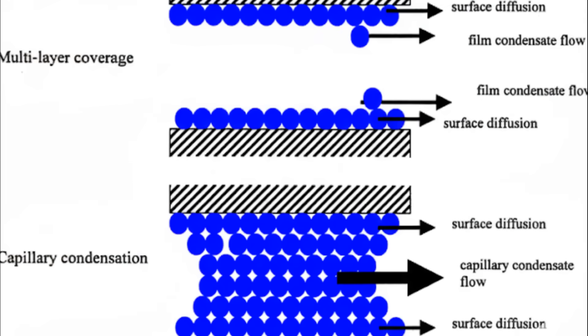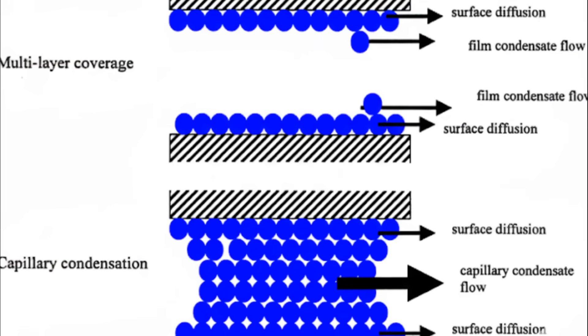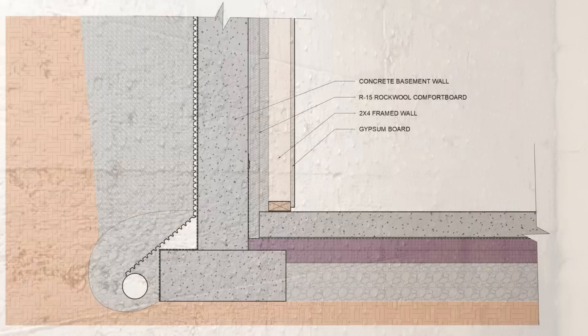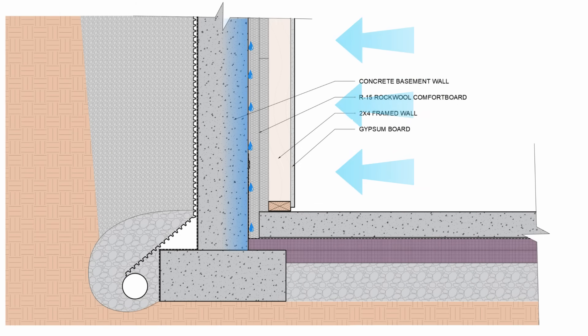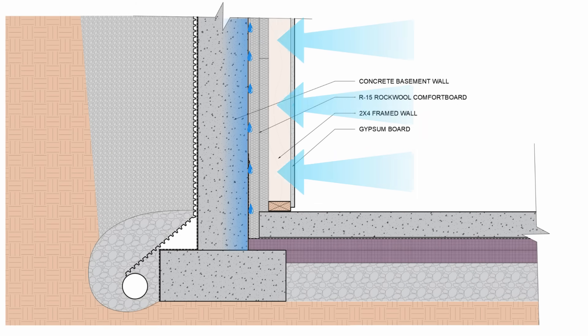Again, this is first going to appear as capillary condensation, and then you'll start to see it beading off the surface of that concrete. We are basically increasing the moisture content of that concrete if we don't stop warm, moisture-laden air from the interior from coming into contact with that surface.